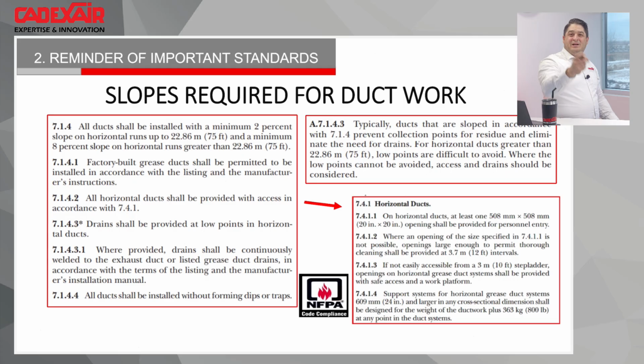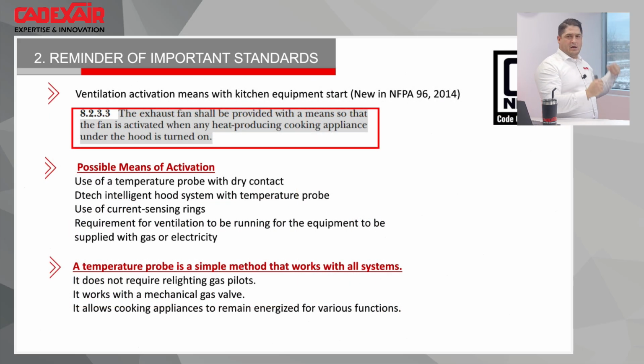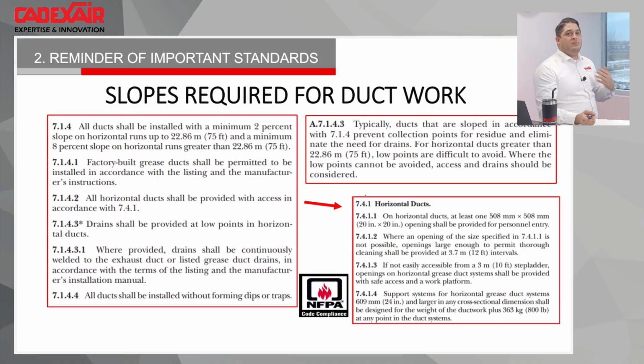But there's a way it's written that if you have a 20 by 20 access door, the guy can come inside of the ductwork and do his job, and you only need one at each extremity. In our specific case, it was a 50-foot long ductwork with a curve in it, and it was 24 by 24, and they put two 20 by 20 inch access doors. So I will tell you something. It's sure I don't fit in that kind of hole, and I will never ask one of my employees to do something I'm not ready to do.